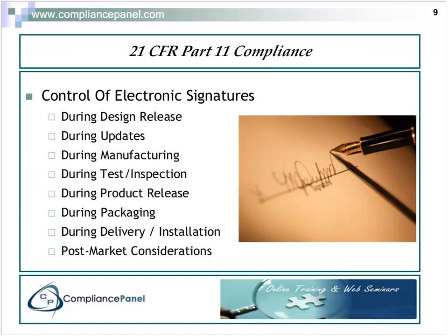And at this point in time, I'd like to talk a little bit about 21 CFR Part 11, although this has been in evolution for a long time now. I believe the last revision that I know of was in April of 2004. And here they're just looking for a validation of your system to ensure the accuracy, reliability, and the consistent intended performance of electronic records.